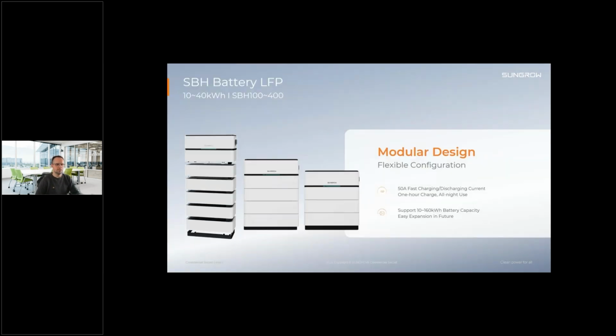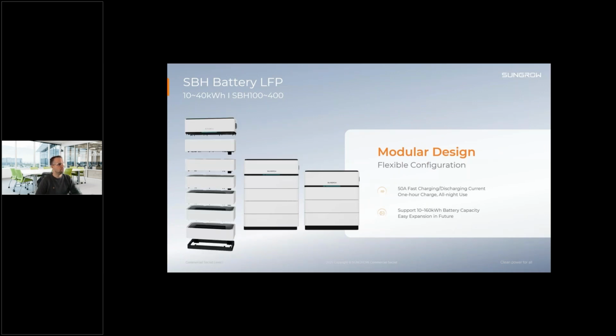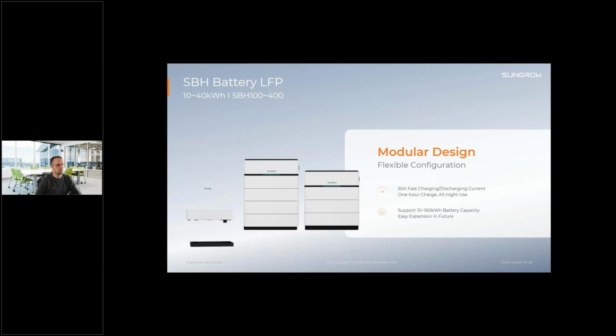Now we go to the SBH battery, which is compatible with our SHT. It can be from 10 to 40 kilowatt hours. It's possible to connect two parallel towers to the SHT, meaning we could have up to 80 kilowatt hours of battery per device. The big advantage of this battery is 50 amps of charging and discharging, if conditions are fulfilled, which means we could fully charge it in 1 hour.